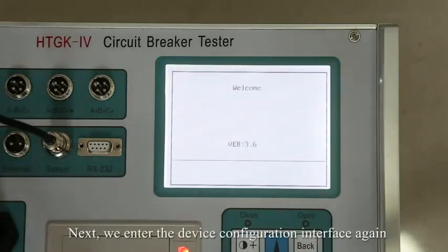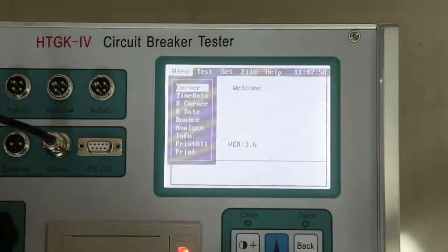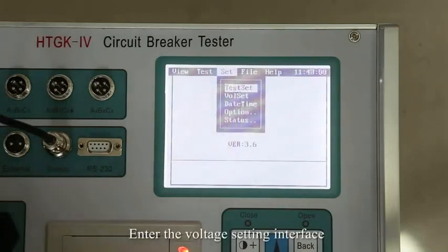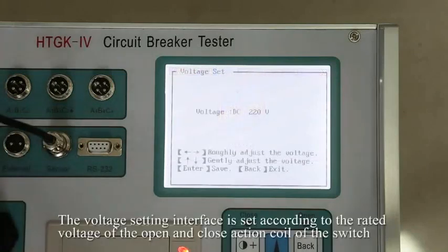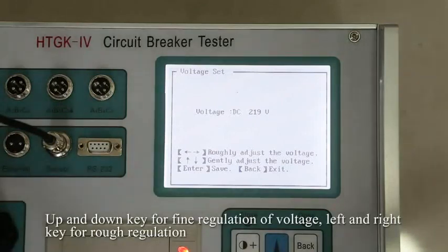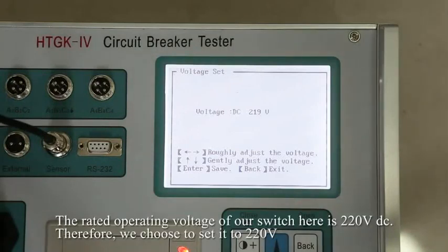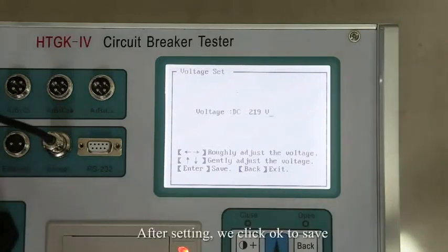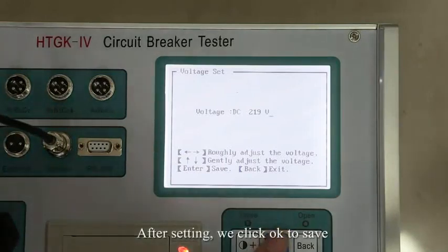Next, we enter the device configuration interface again and enter the voltage setting interface. The voltage setting interface is set according to the rated voltage of the opening and closing action coil of the switch. The up and down keys regulate the voltage by column, and the left and right keys regulate by row. The rated operating voltage of our switch here is 220 volt DC, therefore we set it to 220 volt. After setting, we click OK to save.